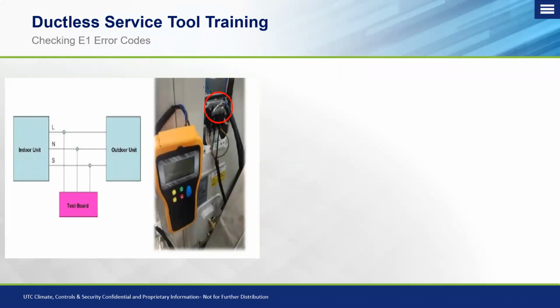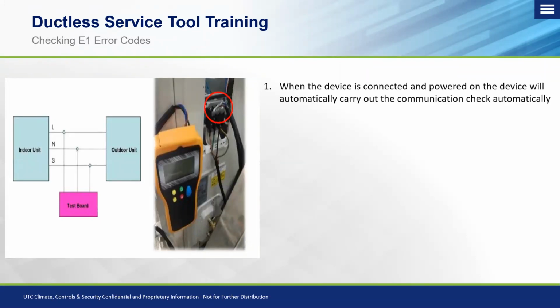Okay, so when you're testing the E1 error code, you can see on the pictorial that your test board is actually the service tool, and you're going to plug in on the L, N, and S to be able to test this. As soon as you wire this L, N, and S to the bus bar, you'll see these actually do come with female connectors that will plug directly in on the top side of the bus bar. If you don't want to use these, you're more than welcome to cut them off and strip the wire so it's there to get underneath. Of course, you want to make sure you have a good, secure electrical connection. So when the device is connected, you set your settings to your L, N, and S on your service tool.